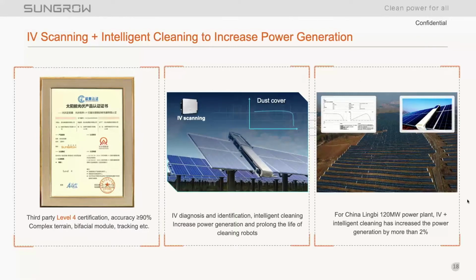So a couple of things to boast about with the inverter is that back in 2016, our online IV curve scan obtained TUV certification, and we were the first inverter manufacturer to achieve that. And we're now the first inverter manufacturer to have achieved the level 4 certification for the online IV curve trace. And basically that shows that the accuracy is continuing to increase with that online IV curve scan.